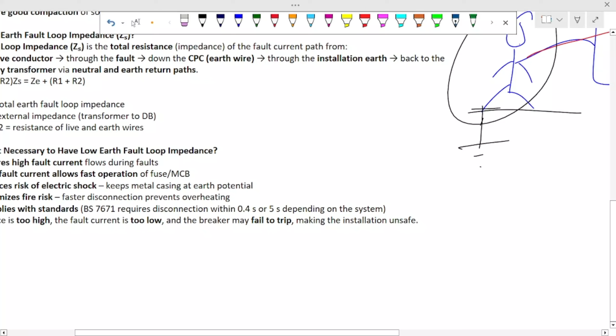The fault will just sit on this metal body, waiting for whoever touches it, to get the person shocked. But if there is this path, it will ensure that the fault current flows through this and not just stays here waiting to shock someone. So it ensures high fault current flows during a fault.